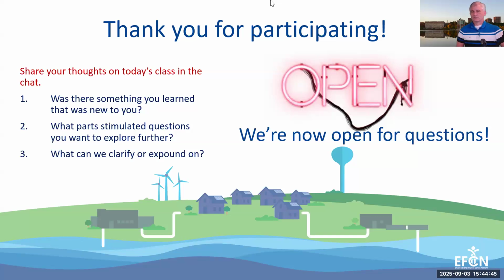Yeah, I like that. It's a good question. Let's say you're operating your system and it's always 1.0 milligram per liter every day, and all of a sudden that drops, and you go out and you check and everything's working, the chlorine pump's working, and it drops to 0.1 or 0.